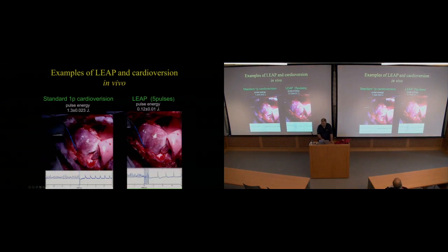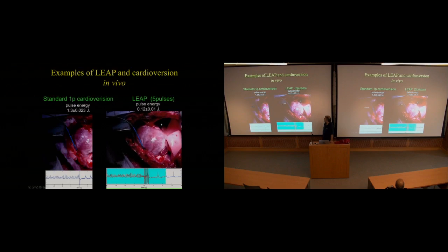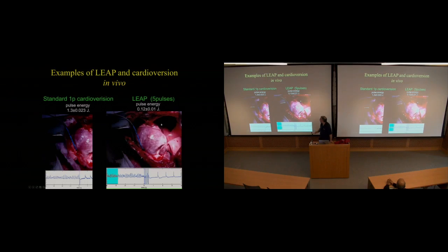So let me show it one more time. We can induce clinically an arrhythmia. So it's normal, but we induced an arrhythmia. Now here's the view of the heart like that. So now we'll do the same thing, but we're going to use 10% of the energy, with 5 pulses. So it terminated the arrhythmia too, but in this case you see there was very little, so the whole body didn't jump, right? The whole body was relaxed.